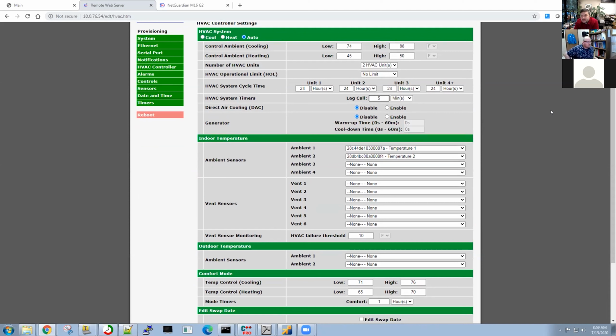That's a 5-minute keep out, because we learned a lot building this originally. One of those things was you didn't want to immediately go to lag, because the heat had some momentum—the lead unit was revving up and starting to do its cooling job. So we give it this amount of minutes; you can ratchet it down to just 1 if you want, but that's the time it's not going to lag immediately. The original version of the code was if it didn't rise above 88, as long as it got back into the window, it would never call the lag, which was a problem.